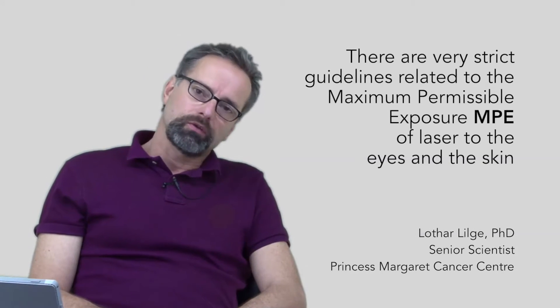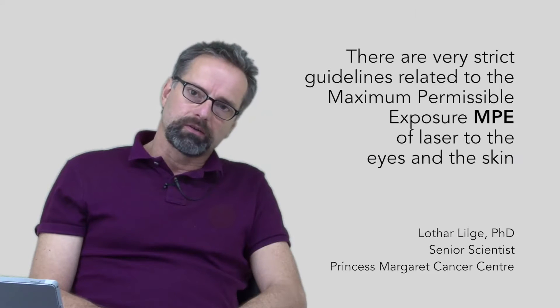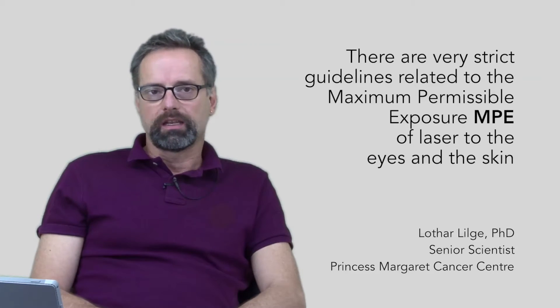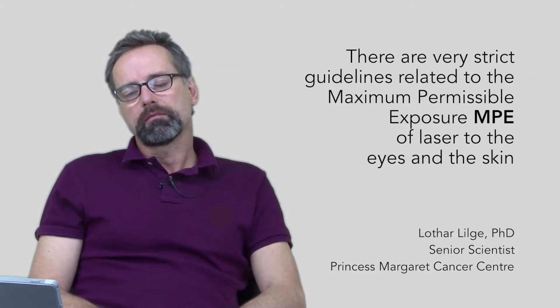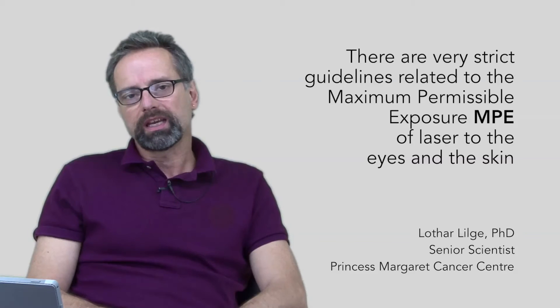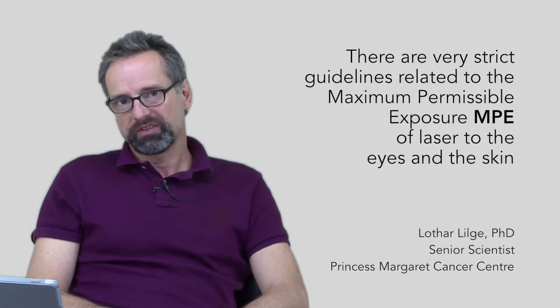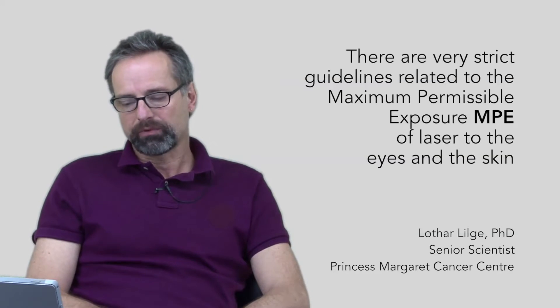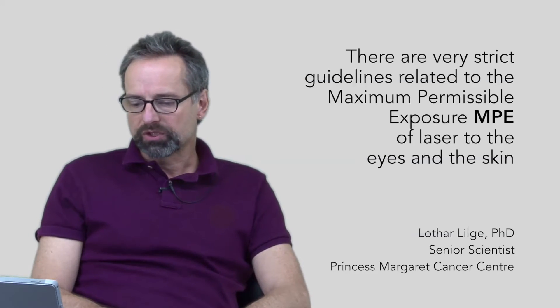There are very strict guidelines related to the maximum permissible exposure not only of the eye but also of the skin. Because in low-level laser therapy we are always looking at the exposure of the skin as the primary target, we should focus on skin exposure first. The exposure of the eye should not be intentional.